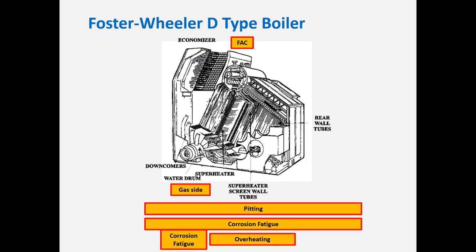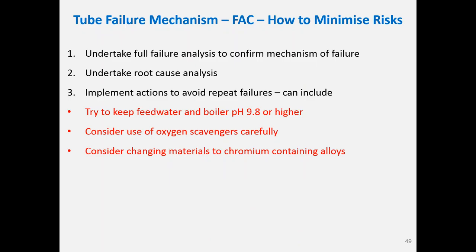To address FAC: do a full failure analysis and root cause, then keep feed water and boiler pH at 9.8 or higher — that drives you down the solubility curve. Consider the use of oxygen scavengers carefully — if you are using oxygen scavengers and having FAC failures, you probably need to reconsider that approach. Sometimes you can't change the chemistry enough, so you replace tubes with a higher chromium content material. Instead of carbon steel, you go to what we call P11 or P22 — one-and-a-quarter or two-and-a-quarter chrome — which armors up the boiler and provides additional protection, and you shouldn't have another failure again after that.